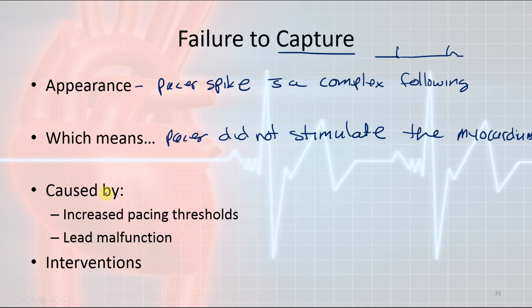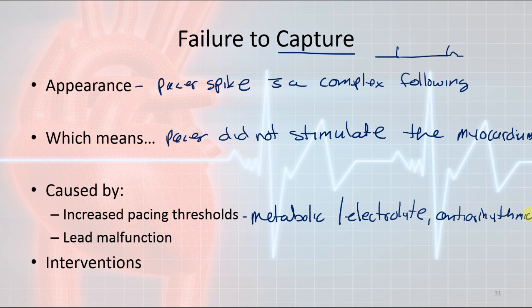Usually this kind of problem is caused by increasing pacing thresholds, which could usually be caused by metabolic or some kind of electrolyte problems. It could also come from antiarrhythmics. So if a person is on some type of antiarrhythmic for their heart, it could also come from where the lead attaches to the myocardium. Sometimes that will develop some fibrous tissue, so fibrosis at the site. Lead malfunction could occur also, which means the leads could be broken or damaged somehow. They could come dislodged. They could lose a connection between the pulse generator and the lead, or the lead and the myocardium. Those are the biggies for the lead malfunctions.